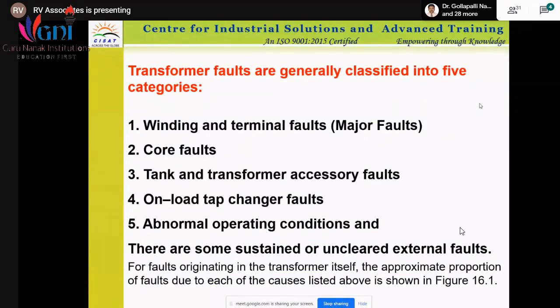Transformer, it's an electromechanical device. So there are some mechanical parts, there are electrical faults. Whatever the faults are there, faults will be categorized in both electrical as well as in mechanical systems. So the electrical system only has a winding, so we have a winding fault. Another is a mechanical fault. It can be a core fault. It can be all support system faults, auxiliary systems faults. So these are the 5 categories that we classified in transformer faults.